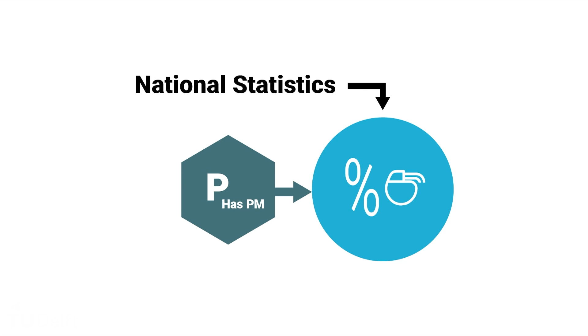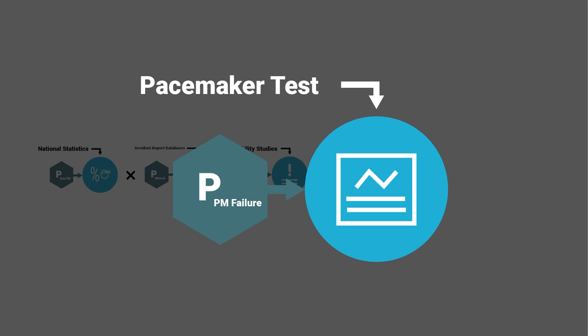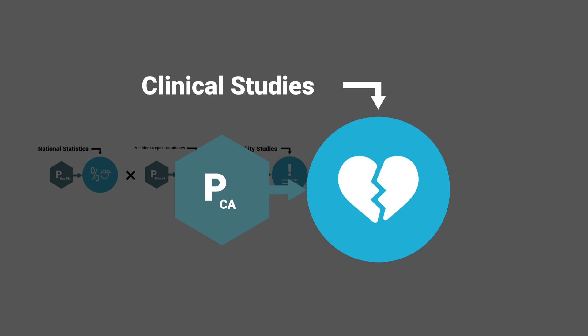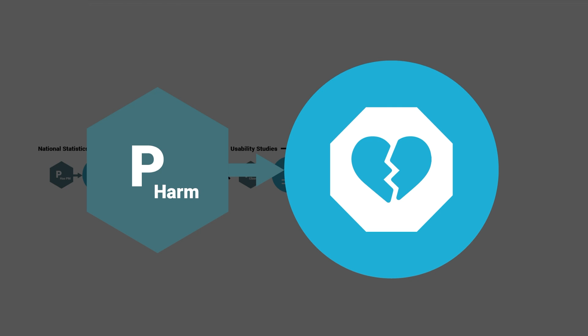pacemakers going unnoticed. Next, a usability study could show how often trained users put the return electrode close to the heart in general. We could use data from pacemaker electrical safety studies to get the probability of a pacemaker failing due to an electromagnetic pulse. And finally, we could check clinical, epidemiologic and case studies to estimate the probability of a patient going into cardiac arrest if a pacemaker fails at all. Now, the product of these separate probabilities from all kinds of sources would give us the probability of cardiac arrest following the overlooking of a pacemaker, like this.